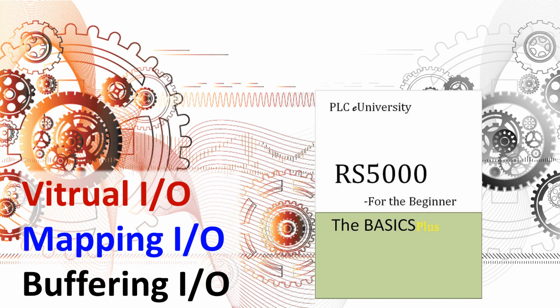To avoid that, they do something called buffering I/O, and that is where in the very first rung in your program, you take and copy the snapshot of an input module into another tag, and then you use that tag and the bits of that tag to write your program with. So you're not directly using module-defined tags. You're transferring the module-defined data into just an integer or double integer. So that integer or double integer only gets updated once at the beginning of the program.